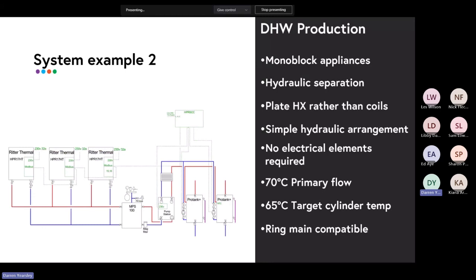We do individual pumping on the cylinders, so you've got redundancy rather than just having one pump. And it also means that you don't have to do a reverse return circuit to balance the flow in any of these. The heat pumps have got their own circulating pump, so you don't need reverse return on the primary. And then the hot water cylinders have their own circulating pump, so you don't need reverse return on the secondary either. So very, very clean in terms of system design. And yeah, very clean in terms of system design.